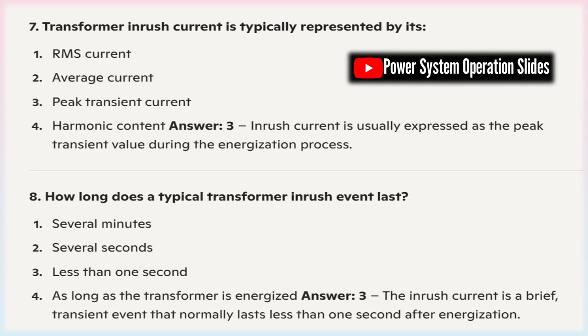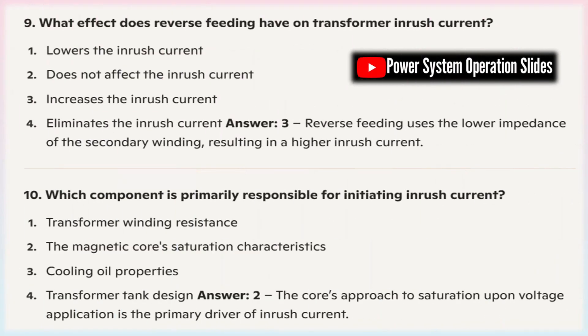Though the best practices will vary somewhat depending on the transformer you are using, there are several steps that can be taken to manage inrush current and mitigate its effects. Here are some common practices. Step-up transformers: If your project requires a step-up application where the applied voltage is lower than the induced voltage, you may need a step-up transformer. Step-up transformers are designed to reduce inrush current in the case where a typical reverse-fed transformer would be used.